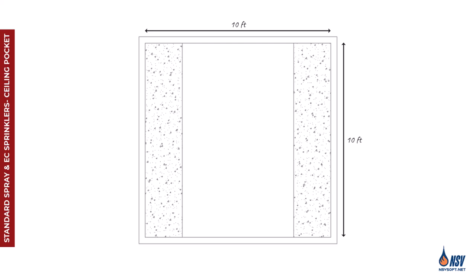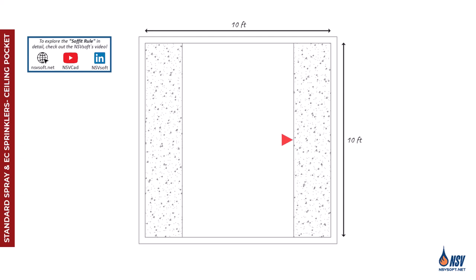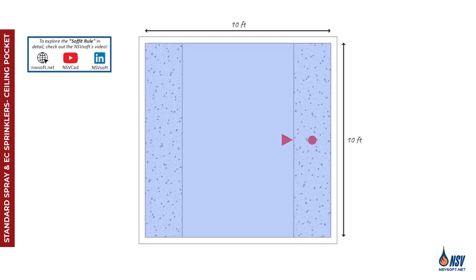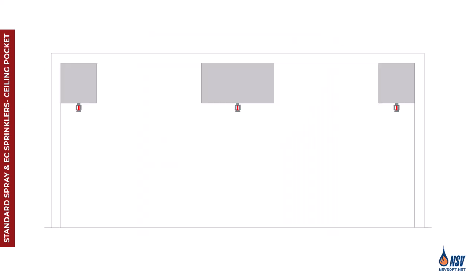It's important to note that if we had overlooked the ceiling pocket allowance, we would have needed to install at least two sprinklers to protect this room, especially since there is no suspended ceiling available for pendant sprinkler installation.